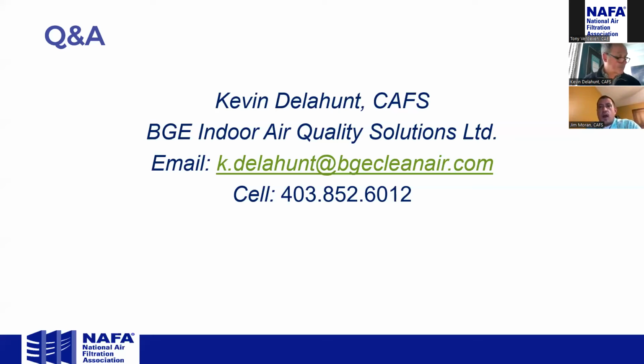Excellent. One question we got a few times here is, what is your recommendation for frequency of replacing air filters? Time-based or? I think there's not one easy answer on this because every building's a little bit different. Even in our part of the world, we can go 6 months in the winter without really changing a filter, and then 4 times in 2 months in the spring when we start to get a lot of environmental burden. So it goes back to something I said a couple times already.